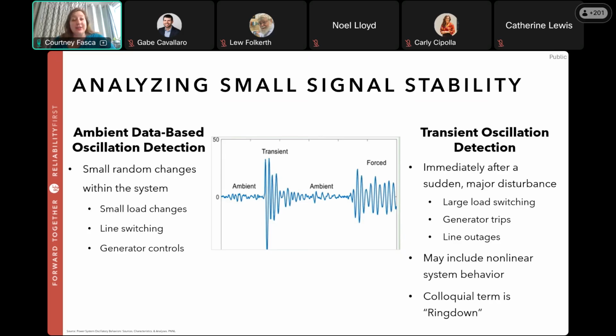So that takes us now to the transient response. Transient response is the grid right after a sudden disturbance. So that's when the pedaler's foot slips off the bike and the team feels the immediate loss of power. Maybe the bike even tipped a bit in the jostling. On the grid, that would be a fault or a line or generator trip, or even a load tripping offline. Sometimes you might also refer to this as the ring down.